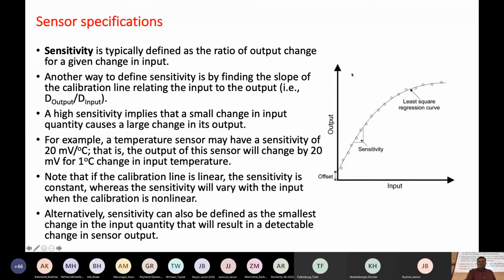In a very simple way, if you have a graph of input versus output, sensitivity is basically the slope. This is assuming that it's a straight line, that there is a direct proportionality between output and input, which may not be the case all the time. For example, you see that eventually the curve is curving here. So you always look at the sensitivity in the straight line part, and you decide that it's sensitive in this region, where you know there is a direct proportionality between output and input. High sensitivity means that a small input causes a large change, and that's what we typically want. If you're trying to detect a very small amount, the signal generated should be large enough that you can actually measure it. If the signal generated is too small, you have errors, and that's why sensitivity is very important. So a temperature sensor may have a sensitivity of, for example, 20 millivolt per degree C.